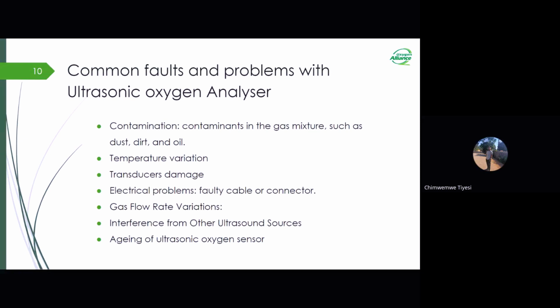The surface of the transducer can get contaminated by dust, oil, or other substances that accumulate on the sensor over time. So one thing to take note of is that ultrasonic oxygen sensors must be stored in a dust-free and clean environment. Another thing that can cause inaccurate readings is temperature variation. Fluctuation in ambient temperature can affect the accuracy of the analyzer. I alluded to this in the earlier slides. Most analyzers have temperature compensation features inside, as I showed when introducing the ultrasonic oxygen sensor, that some have a temperature sensor inside. This is used to compensate for changes in temperature, which may cause fluctuations in the oxygen concentration.